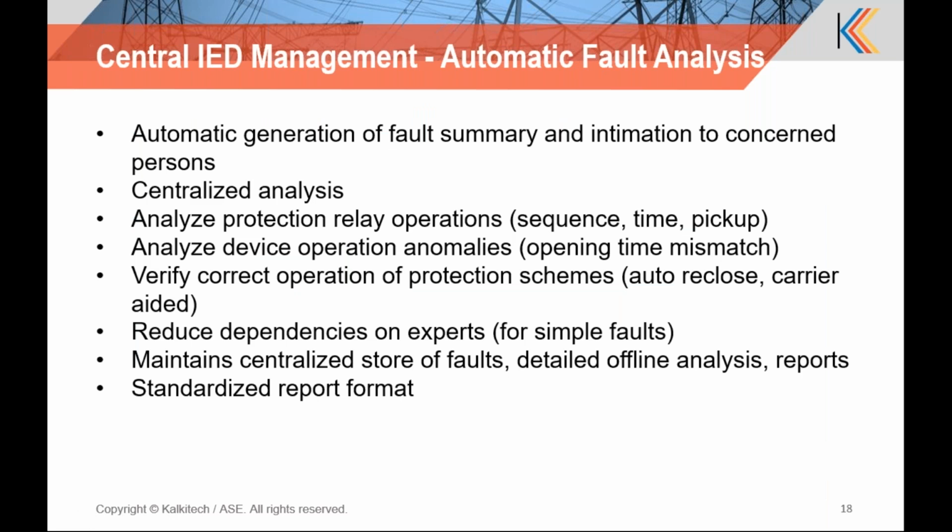Then central automatic fault analysis. As I have mentioned, the PSCS tool provides a very minimal level of COMTRADE viewing and other functionality, and there are third-party tools that enable further analysis. We are using the MyFAS tool from PRDC for almost all the Indian or Asian scenario projects, and we are using another tool, based upon the utility recommendation, for Europe and South American scenarios.